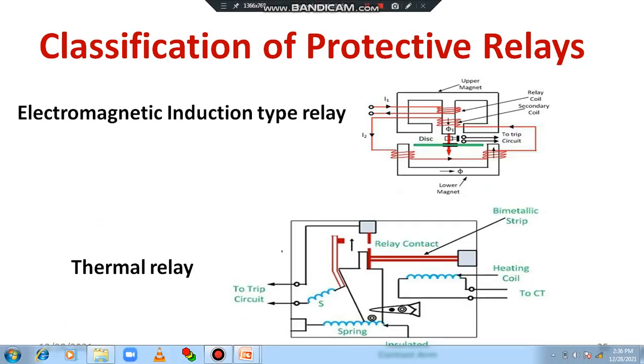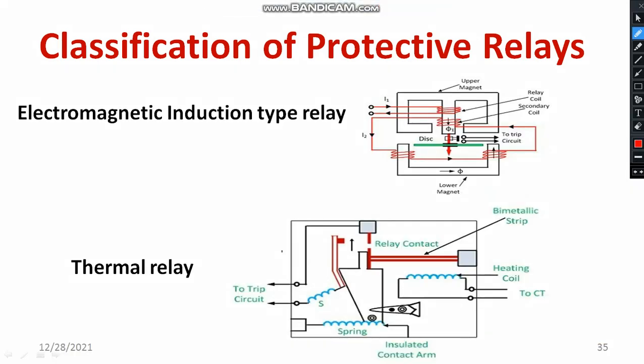The induction type relay works similarly to an energy meter. We have two types of magnets — an upper magnet and a lower magnet. The flux linking in the upper layer is φ1 and the flux induced in the lower layer is φ2. Based on the difference in flux, an aluminum disk rotates. This aluminum disk is directly connected to the trip circuit, whereby the trip circuit is activated. This works based on the electromagnetic induction principle.